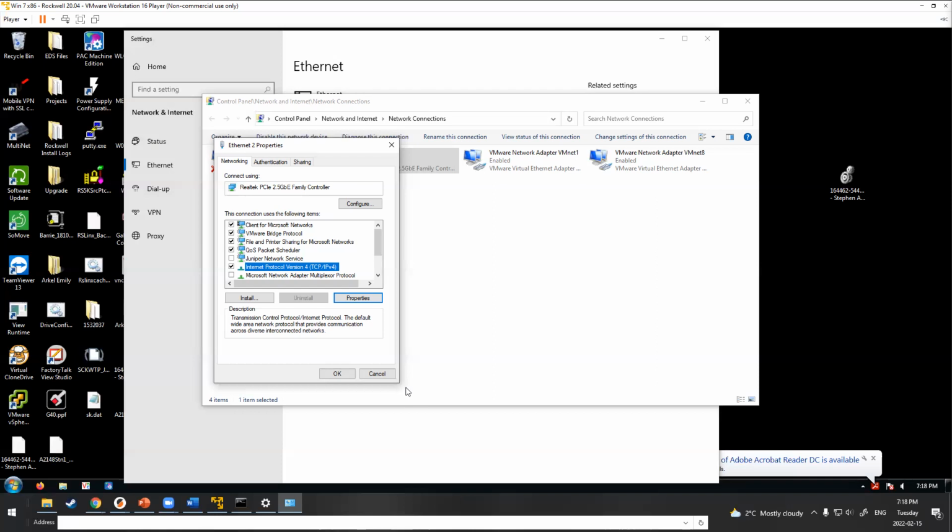So as soon as that machine turned on, it assigned an address to a couple of the computers on the network that were set up to receive them, they conflicted with a handful of their VFDs, and their whole system came to a halt. When it came to a halt the first time, they were in the middle of a pasteurization process.